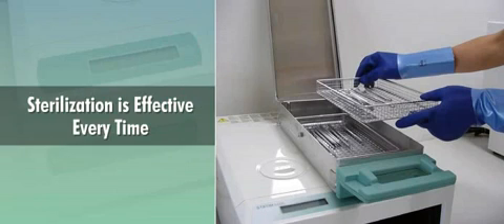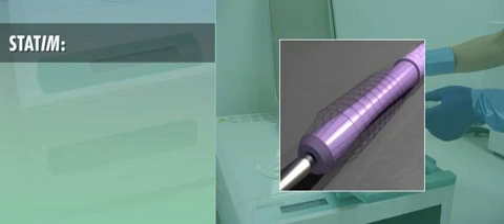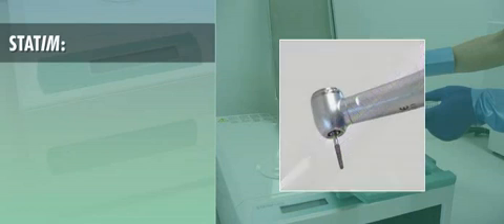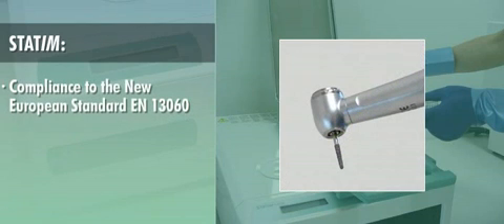Don't let STATIM's quick sterilization time fool you. Sterilization is effective every time, purging all of the air from the fine lumen of dental handpieces. STATIM's biological and physical effectiveness has been proven in tests on a wide variety of dental handpieces, which validate compliance to the new European standard EN13060 for small steam sterilizers.